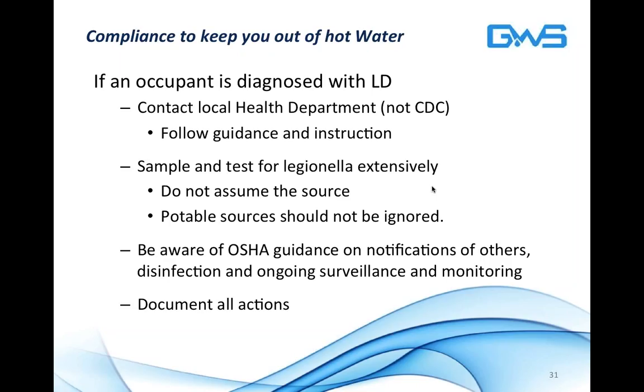If it's been confirmed that Legionellosis occurred from your facility, you need to sample and test for Legionella extensively. Do not assume the source is a cooling tower or something else. It could be in the potable water, and those sources should not be ignored.